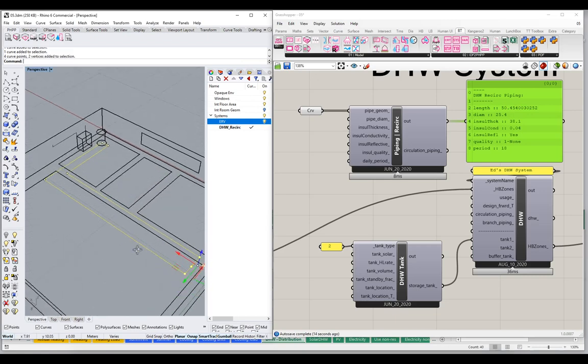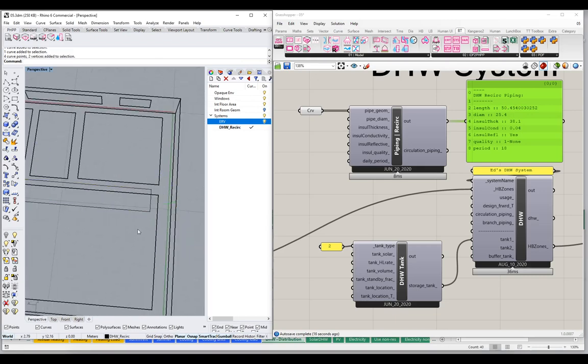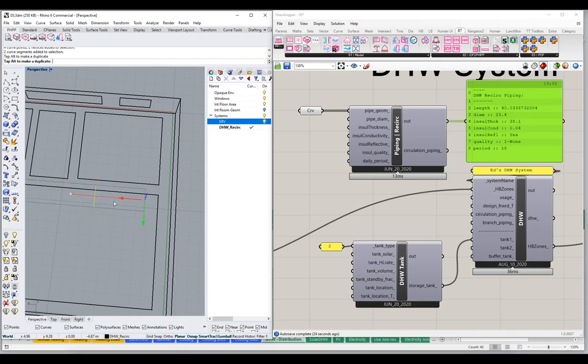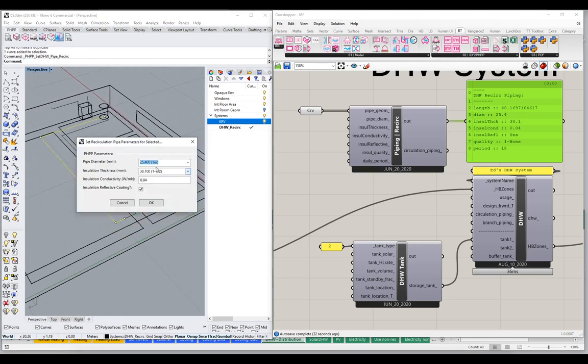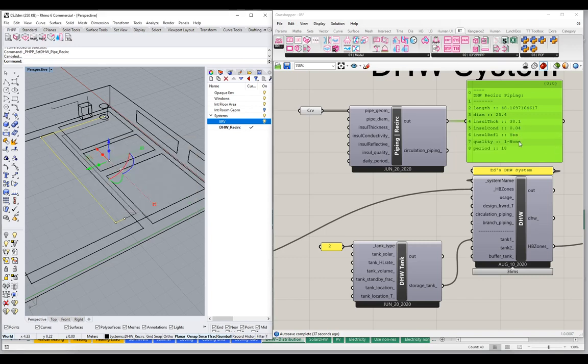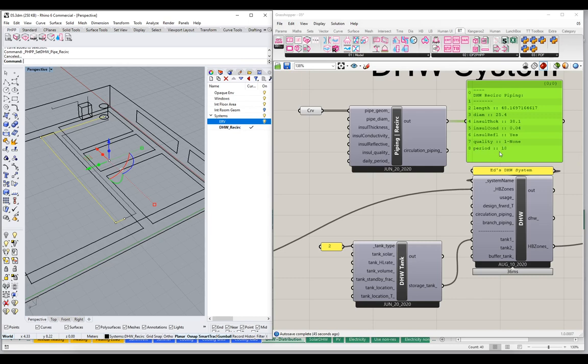Now as output, notice that we are getting a valid domestic hot water recirculation piping object with length. The length is being determined by the 3D geometry — if I modify this geometry and make it a lot smaller, notice that the length just got a lot smaller. It's all linked up and live. The diameter, insulation thickness, insulation conductivity, and reflectivity are all being set by the object parameters. Some elements — insulation quality and period of use — would still be set in the Grasshopper scene.